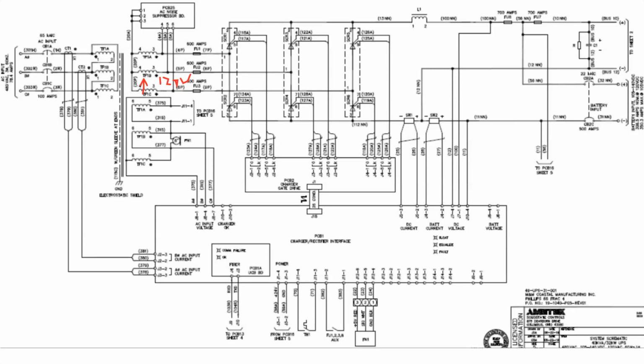So you will have AC still going in at this point here. But now inside our battery charger rectifier, we have 6 SCRs. I can't point at the ones above here because my screen cuts off. It's just the way that Webinar Jam screen is. But there are 6 SCRs here, and that's our switching devices that turn the AC on this side into DC on this side. It really is as simple as that. In the grand scheme of things, it's as simple as that. Now, there is some complex circuitry going on with the charger rectifier interface board and our charger gate drive board, but it is as simple as we have AC on this side and we have DC on this side.